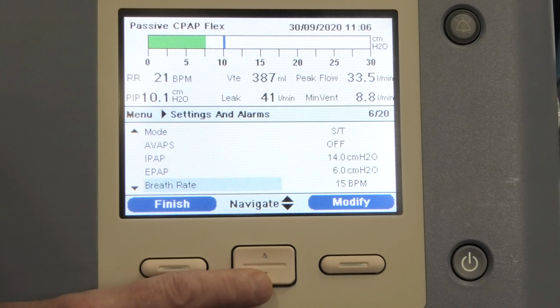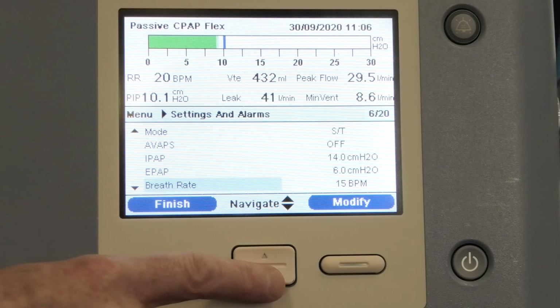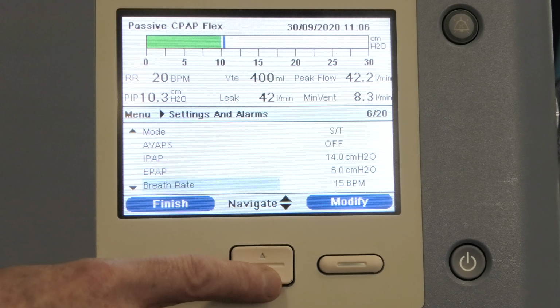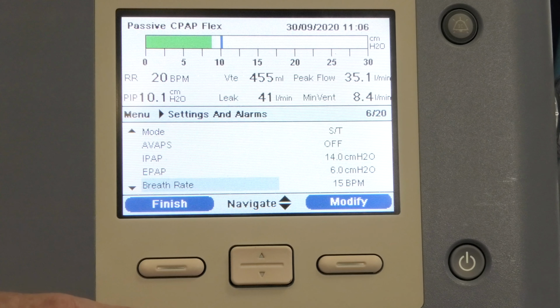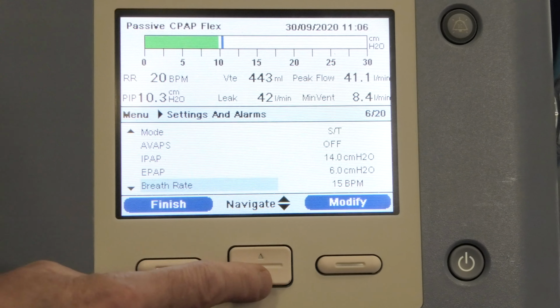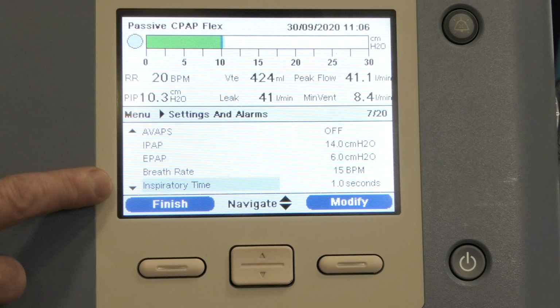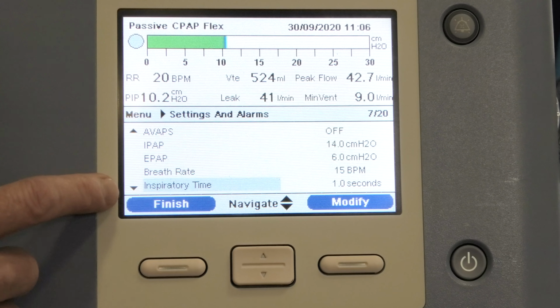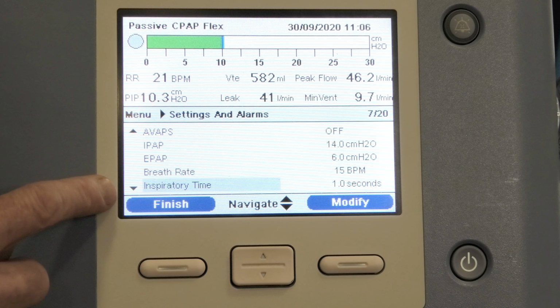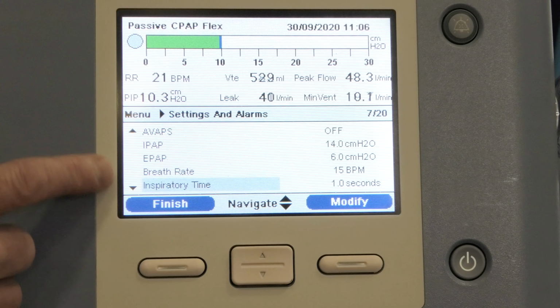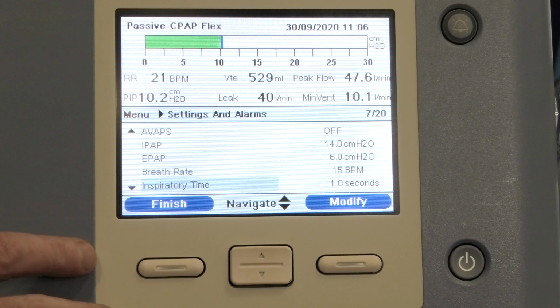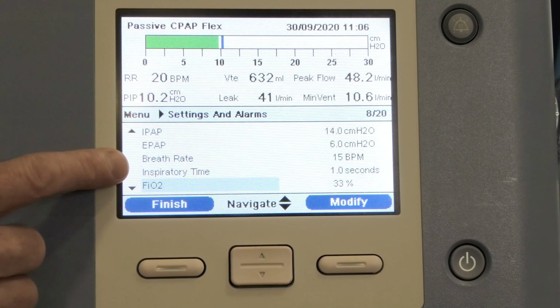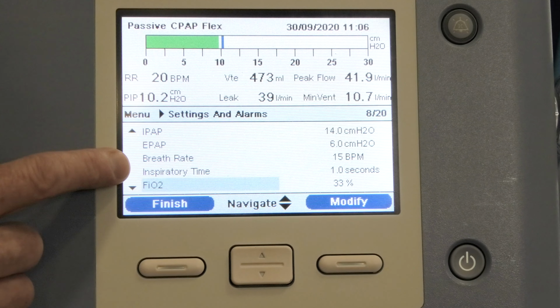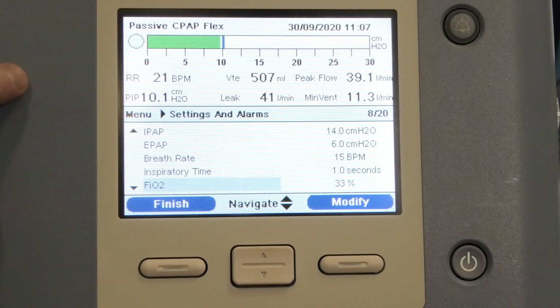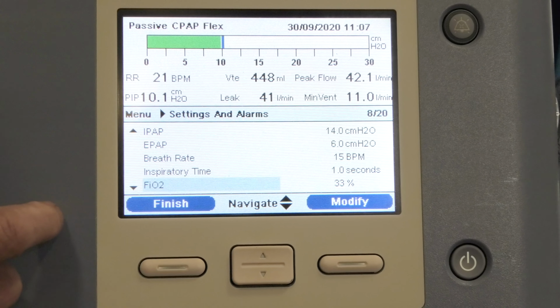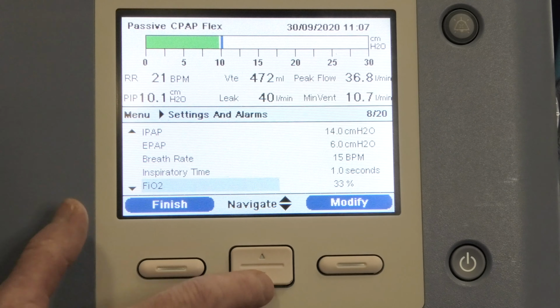We've got EPAP. Breath rate is your backup rate. Your backup rate only kicks in if your patient takes less than 15 breaths a minute. The BTS guidelines say we should set it at 15 breaths a minute. Your inspiratory time is essentially the time that the ventilator inspires for, or blows at the patient for, on a backup breath. On spontaneous breaths, the patient chooses their own inspiratory time. That should be set between 0.9 and 1.2 seconds for a backup rate or breath rate of 15 breaths a minute. There's our FiO2, so if you wanted to change your FiO2, you need to be in this menu.